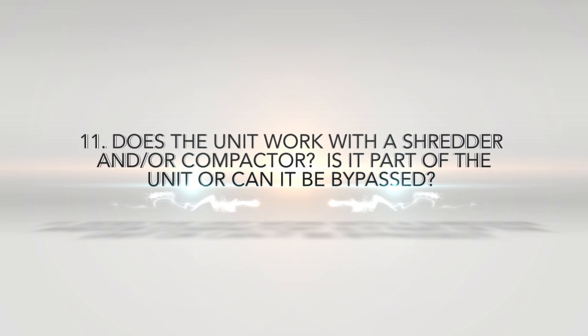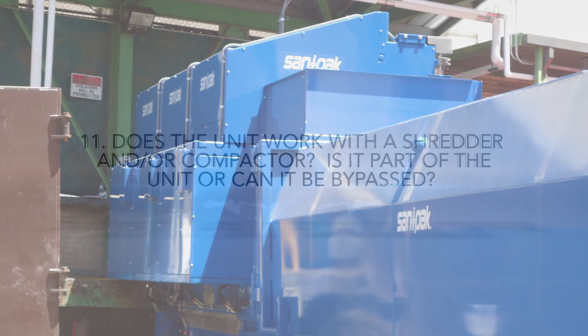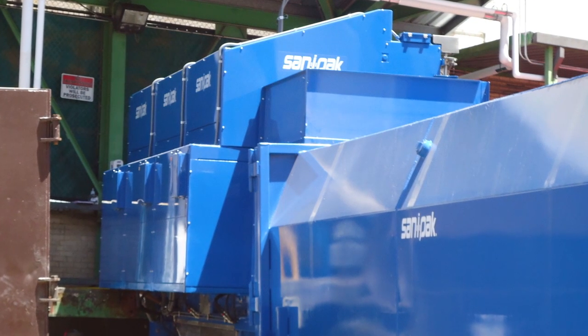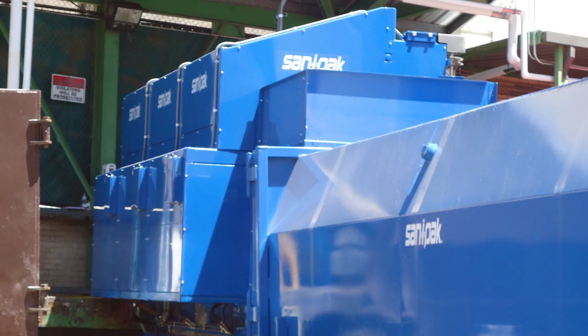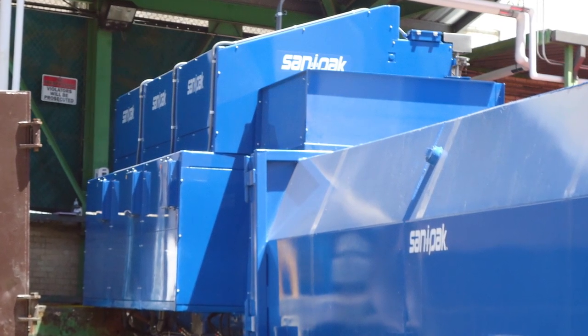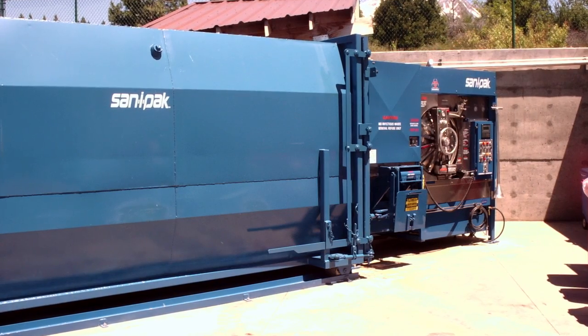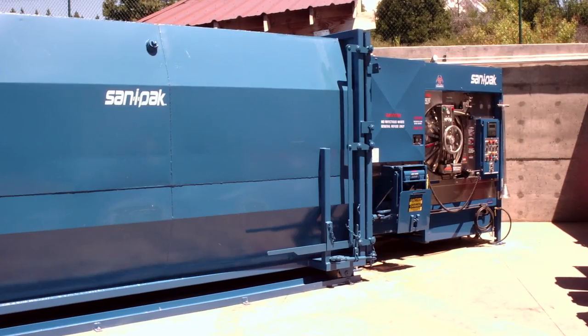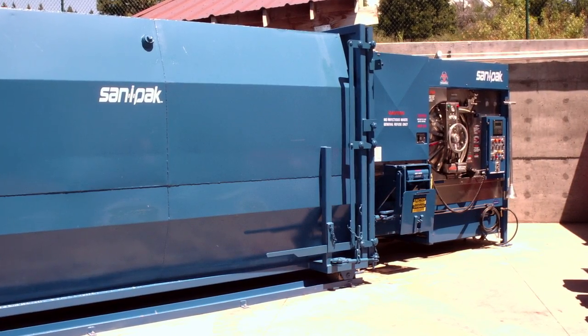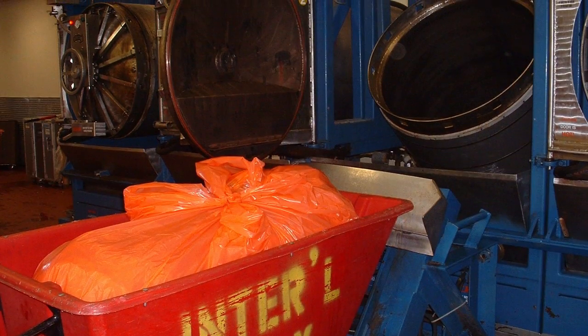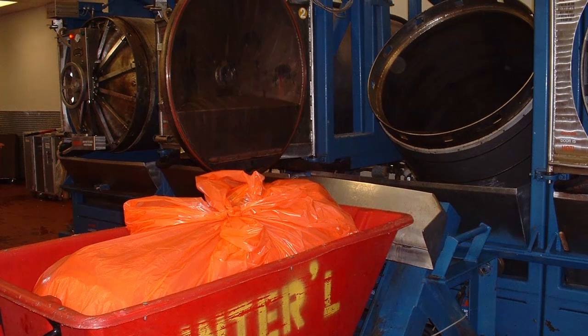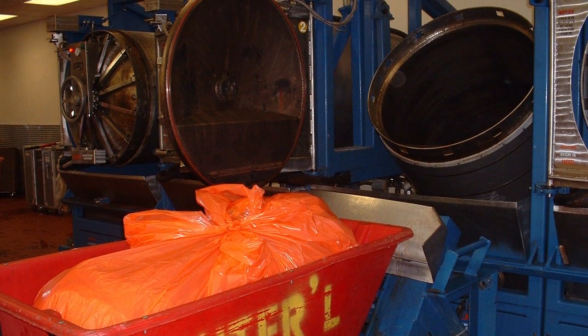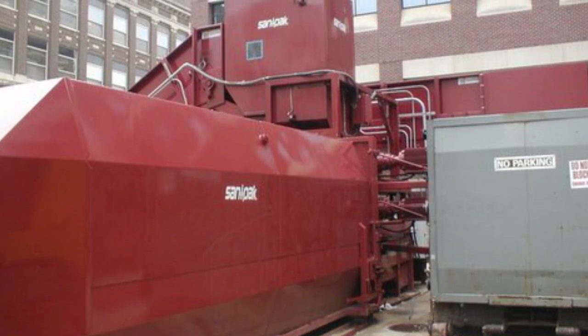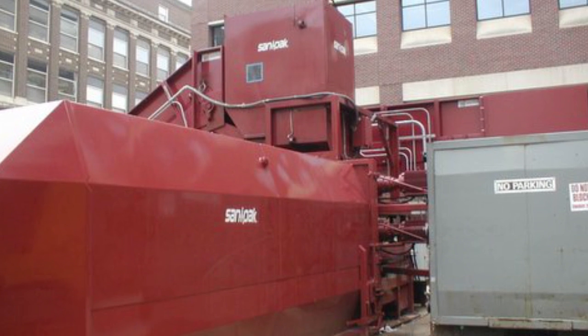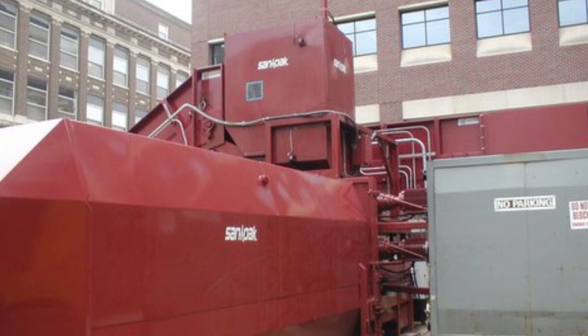SANIPAK units can be designed with a compactor and integrated shredder. However, a majority of our clients select our sterilizer with integrated high-density compactor. SANIPAK has the only advanced autoclave design that can automatically bypass the integrated shredders when the shredders are being serviced. The SANIPAK technology is designed so that the sterilization process is not incumbent of a compactor or shredder, even if the equipment is integrated.